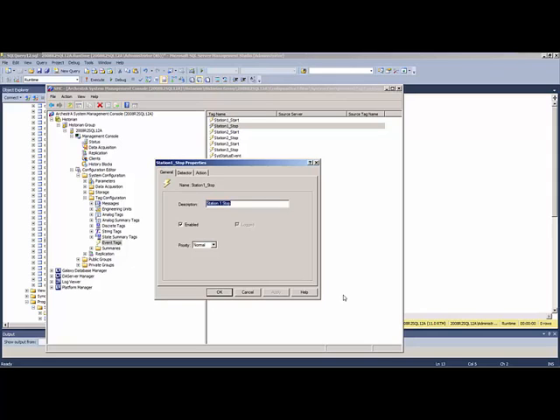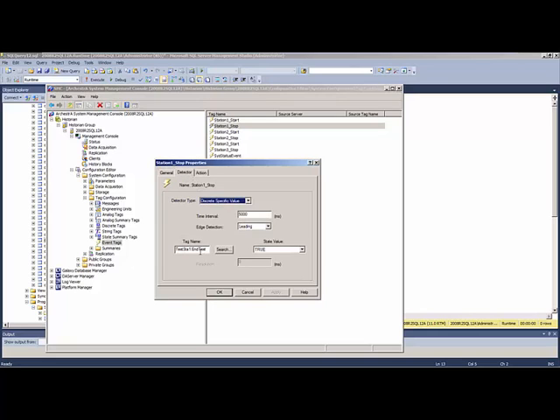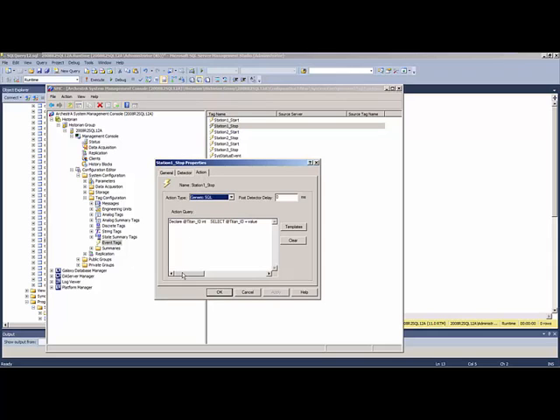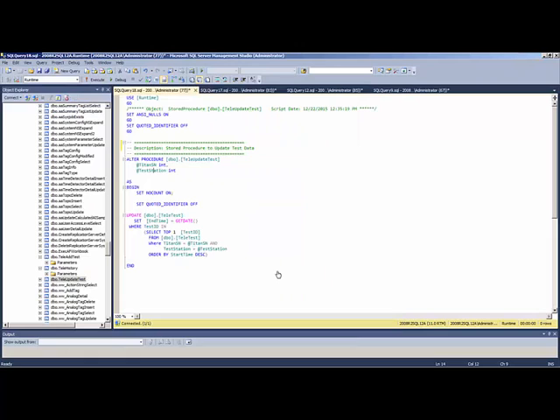We're also using an event tag to execute the stop command to log that information. The detector in this case is going to be the end test bit — it could be a bit coming up from your PLC that's being logged by the Wonderware Historian. The action is also going to take that ID but it's going to update the test and fill in the end time. There's another stored procedure called 'TeleUpdateTest' that puts the end time on there, using the serial number and test station parameters to look up and update that specific test record.